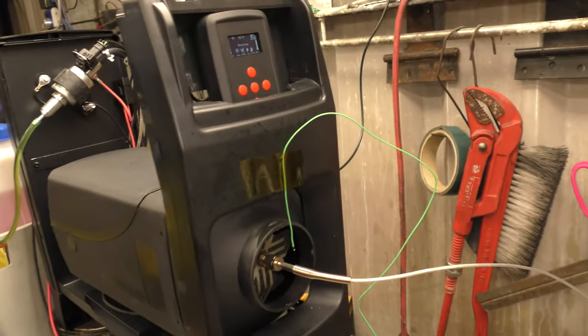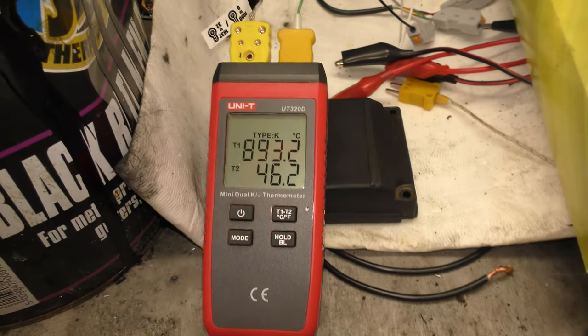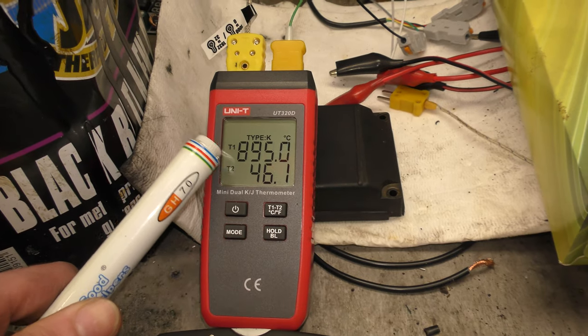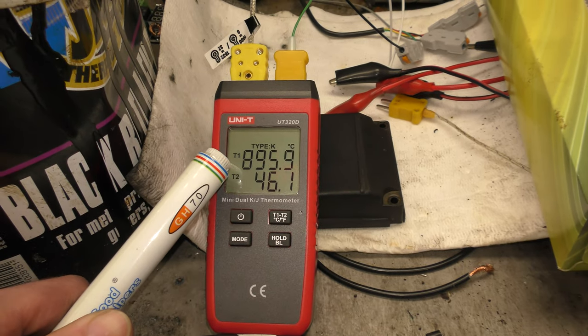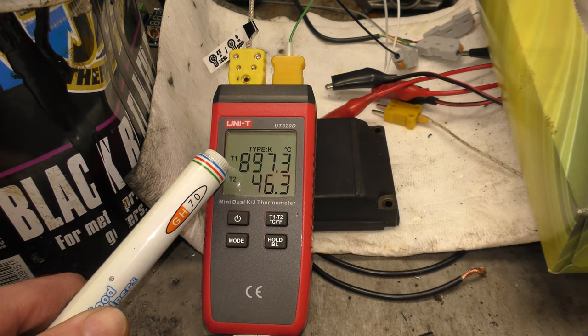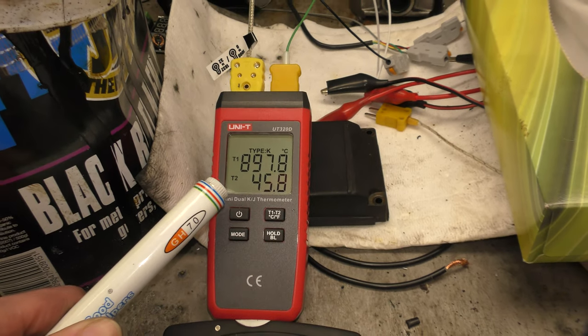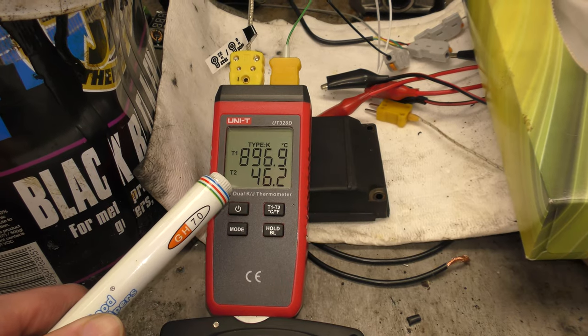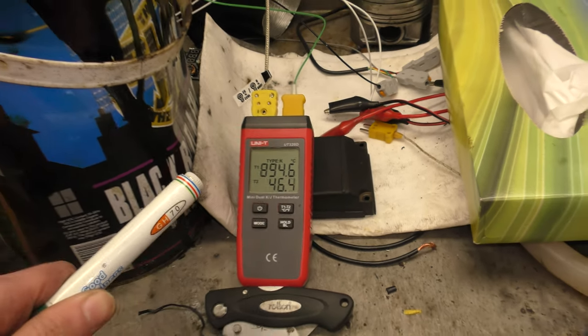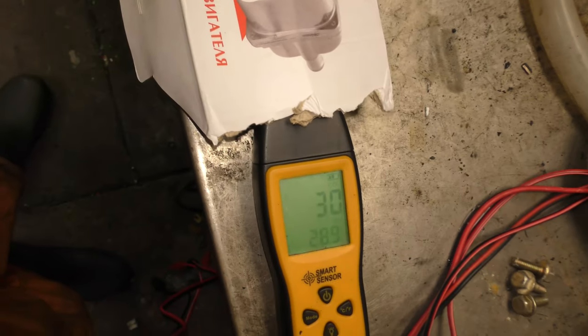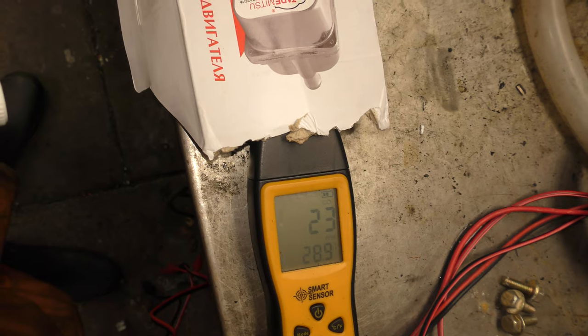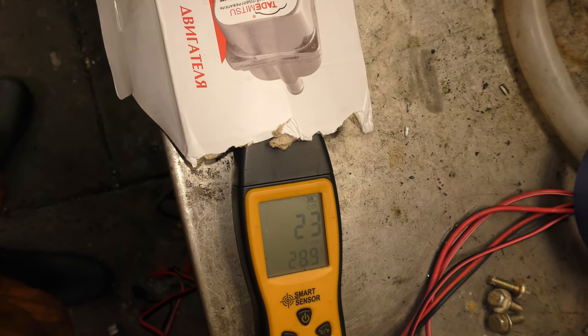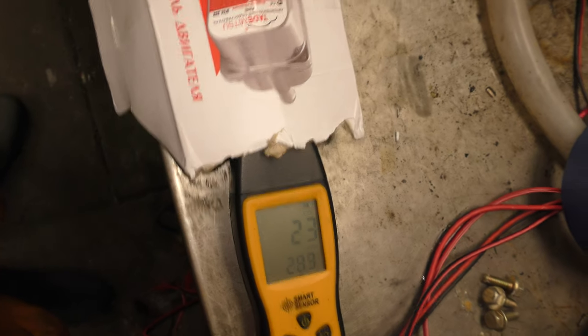Okay, we have a burn chamber temperature of anywhere between 890 and 899. Air output anywhere between 45 and 48 degrees, so 47 is where it's been hovering. Carbon monoxide goes down to like 15 and 30, usually hovering around 25 though.